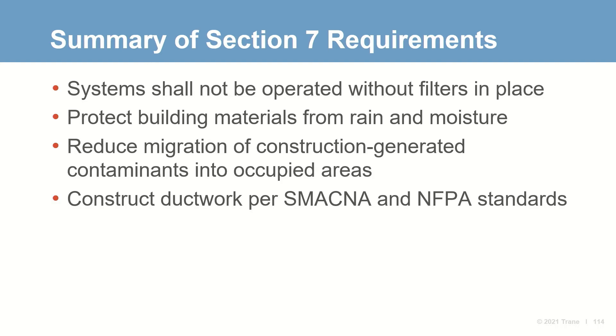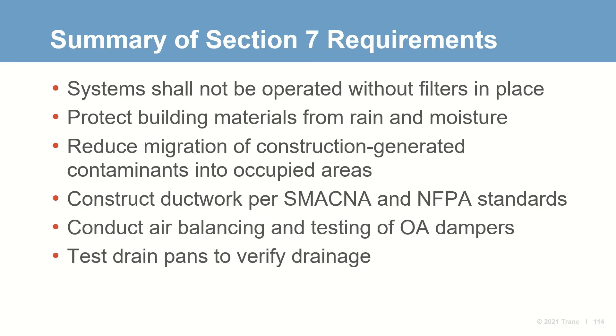Then, when the system is being started up, the standard requires air balancing and testing the function of outdoor air dampers, as well as testing drain pans to ensure they properly drain condensate.